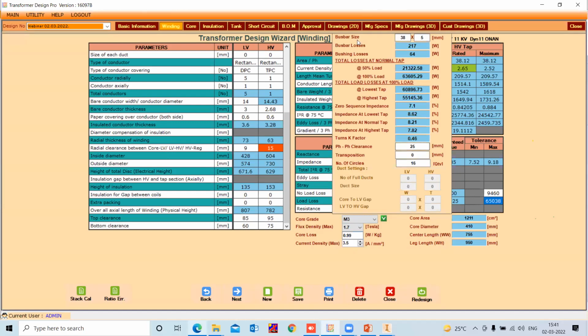Thereafter, in this panel, the busbar size, busbar losses, and bushing losses for 1500 kVA are already added in the stray losses, and here we have given them separately. Thereafter, the losses on 50% load, 100% load, losses on lowest tap and highest tap for 100% load, then the zero sequence impedance, impedance at lowest, normal and highest tap, turns, K factor, phase to phase gap, transposition, number of circles. Here the phase to phase gap is available to edit, and the transposition and number of circles are available to edit.